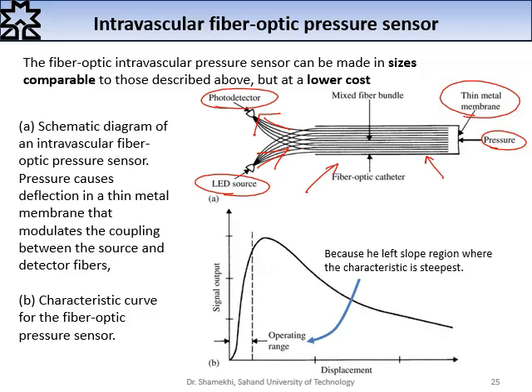Pressure, as I showed here, causes deflection in a thin metal membrane that modulates the coupling between the source and detector fibers. Light will be received here and will be reflected by this thin metal membrane. If this metal membrane is flat, the reflection will be the highest.